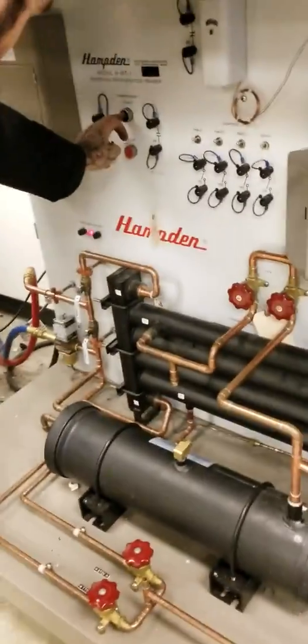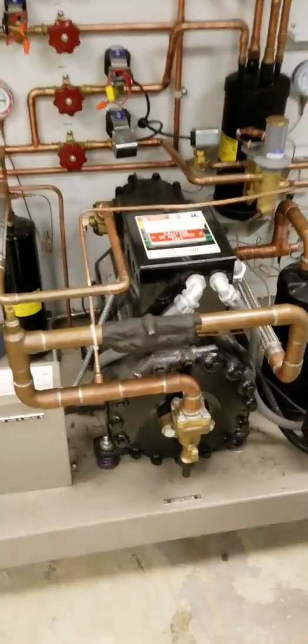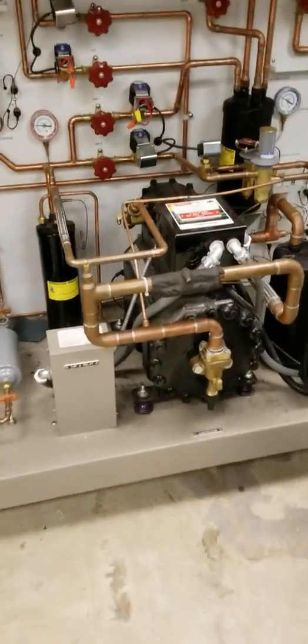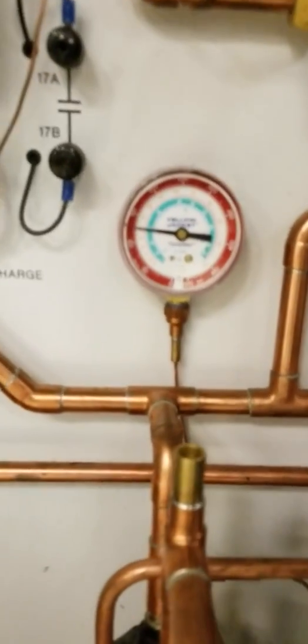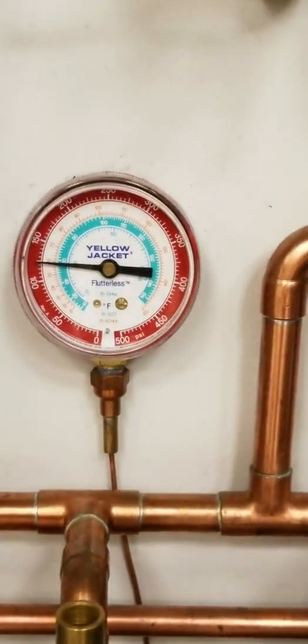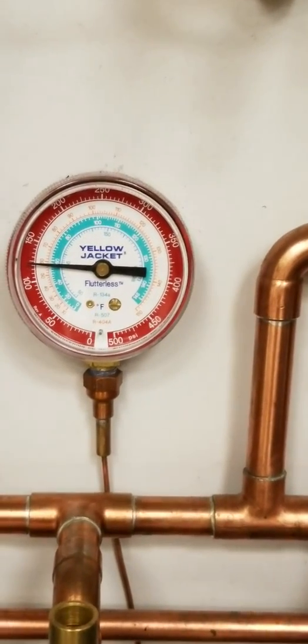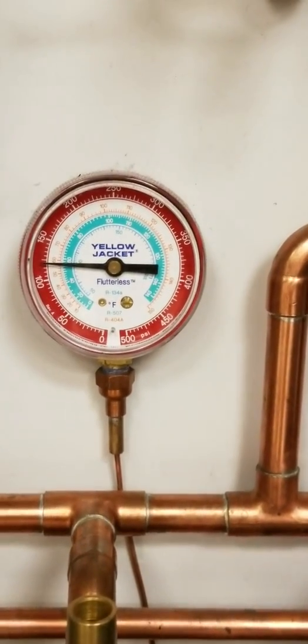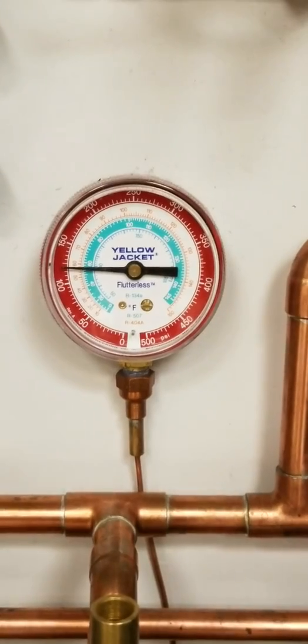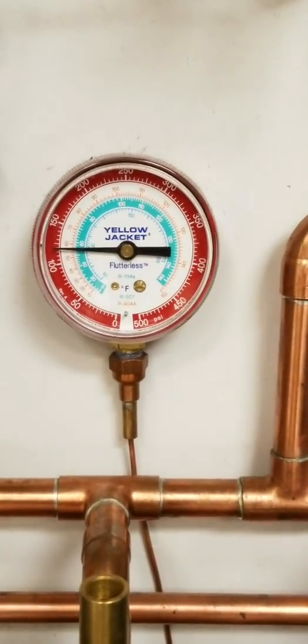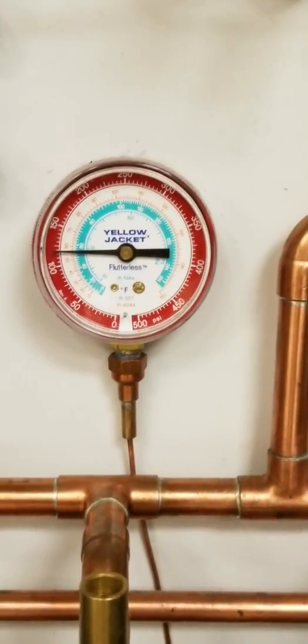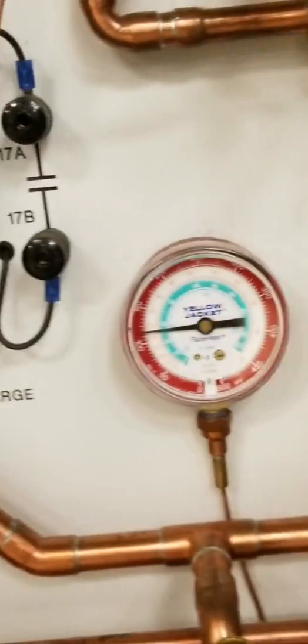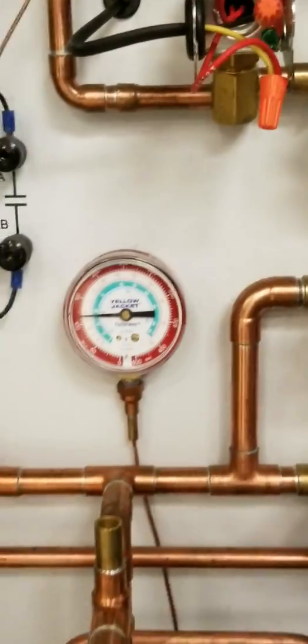Start the compressor. Now it's actually running through, our pressures will stay stable. Now our evaporator fan also has a cut-in. So it's going to allow the pressure to drop, and pre-chill the evaporator, and then turn the unit on. Our pressure's not going up. That's staying stable now. Now watch your evaporator pressure.